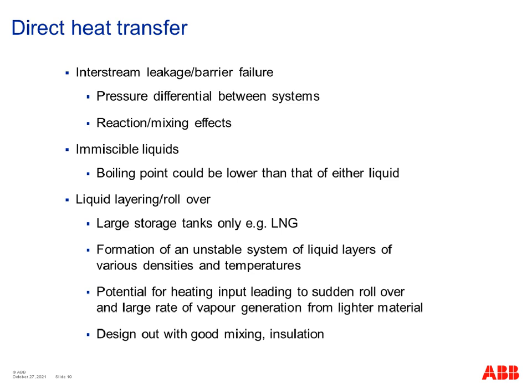So mixing of fluids can also lead to heat transfer effects as well. This is where you have direct contact between the fluids, and of course this could arise in a situation of interstream leakage, barrier failure in the exchanger, which we'll talk a bit more about later, especially if you have pressure differential between the systems. And if this happens, you could end up with a reaction taking place between the 2 sides of the exchanger, or heating effects due to mixing. So your boiling point of the mixed fluids could be lower than that of either liquid, so you could end up with vaporization occurring unexpectedly.